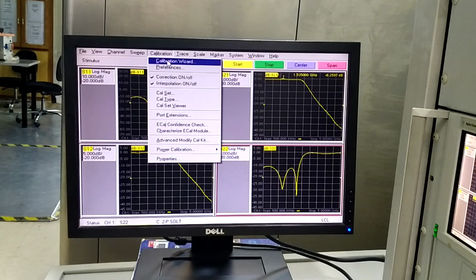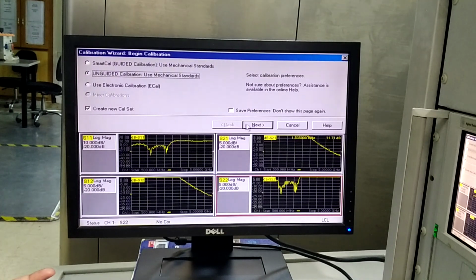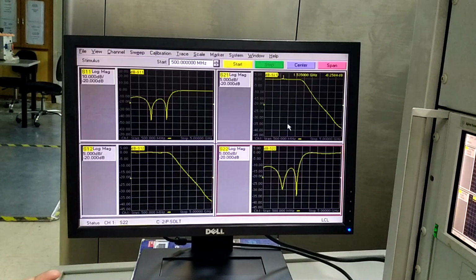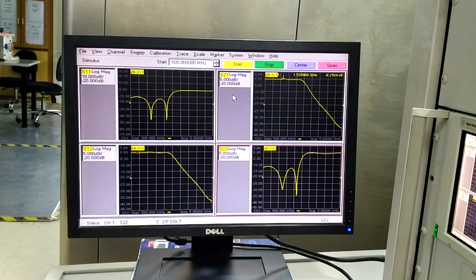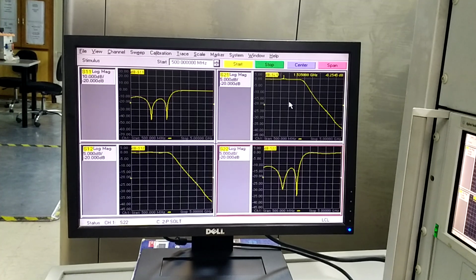So I showed you what the calibration wizard is and how you perform the calibration. Once you are done with the calibration, the next step we did is to validate the calibration, where we used a verification standard, which in our case is a minus 10 dB attenuator. Afterwards, I measured a device under test, which in our case is a low pass filter, and we also saw a very good low pass filter response in our S parameters.